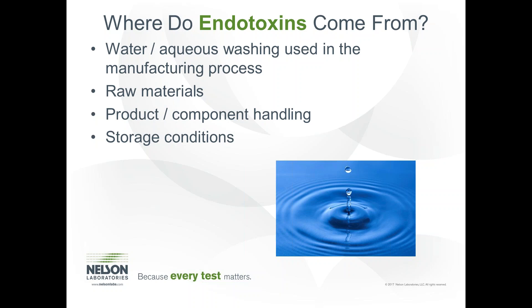Typically, gram-negative bacteria grow in water or wet environments. Any washing used in the manufacturing process can be a source of endotoxin. It can also be present in the raw material or can be deposited on the device during manufacturing or handling.